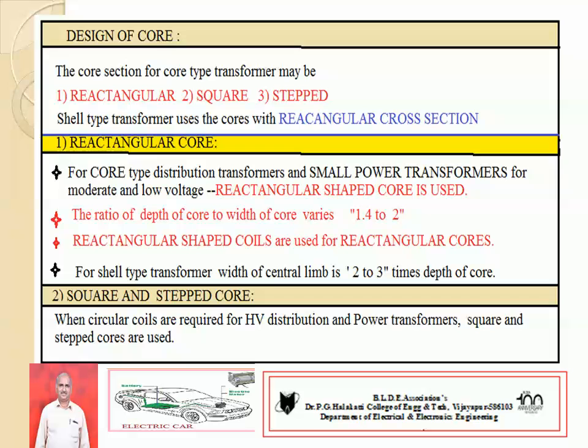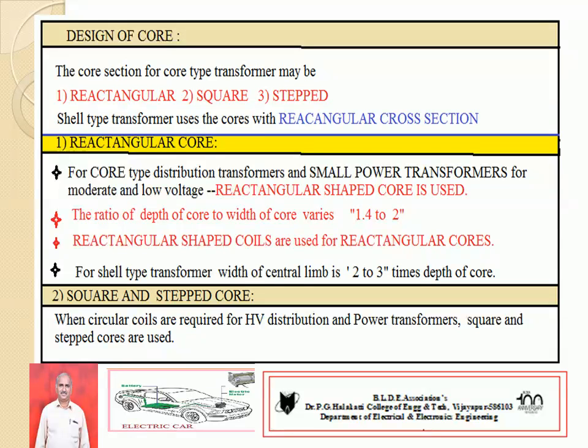In general, we have used rectangular type of core, square core, and stepped core — again in stepped: two-stepped, three-stepped, or four-stepped. The shell type of transformer uses rectangular cross-sections. Rectangular core is mainly used for core type of distribution transformers with small power rating and low voltage rating of transformers.